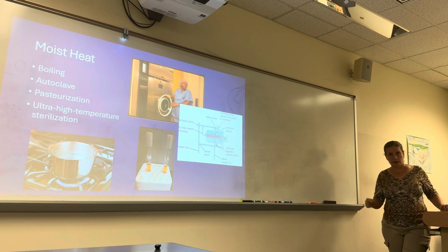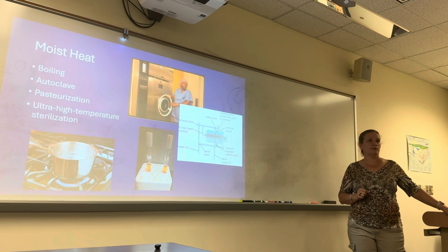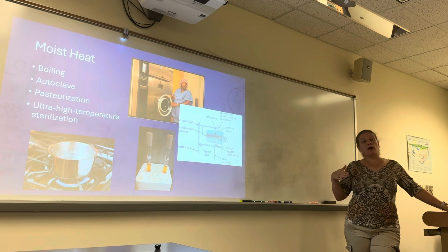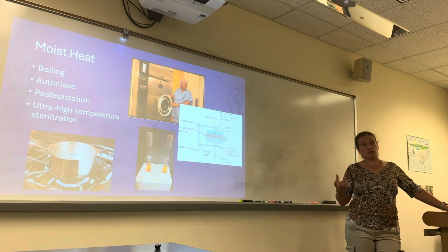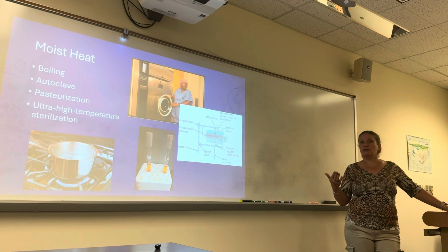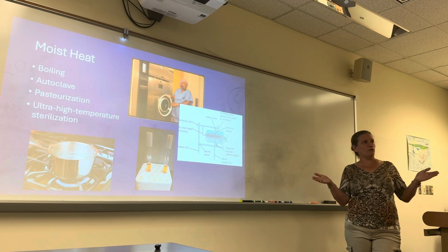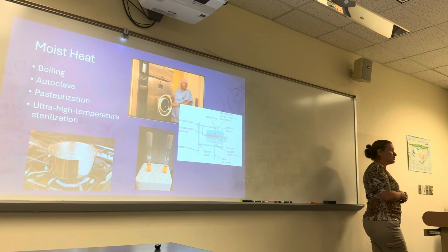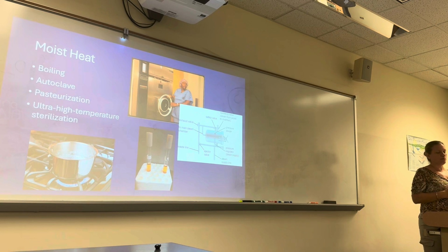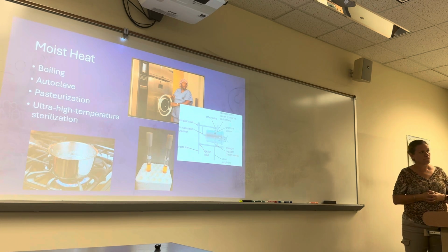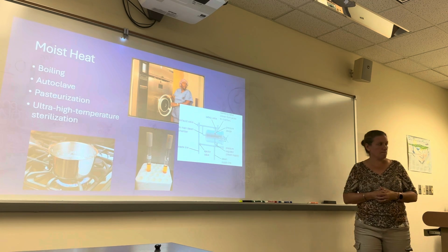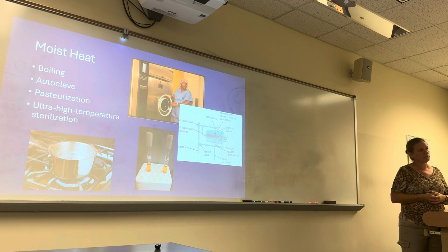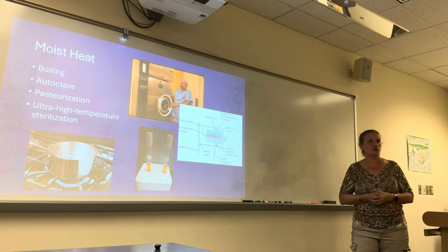It will kill any organisms that are inside. If you really loaded up the inside, sometimes they'll increase the length, going from 15 minutes maybe to half an hour. That's just to ensure that the exposure time has been long enough for everything that's in there. The book says it has to be at 121 to 132, and it's for 20 minutes or more. An autoclave is usually set at 121.